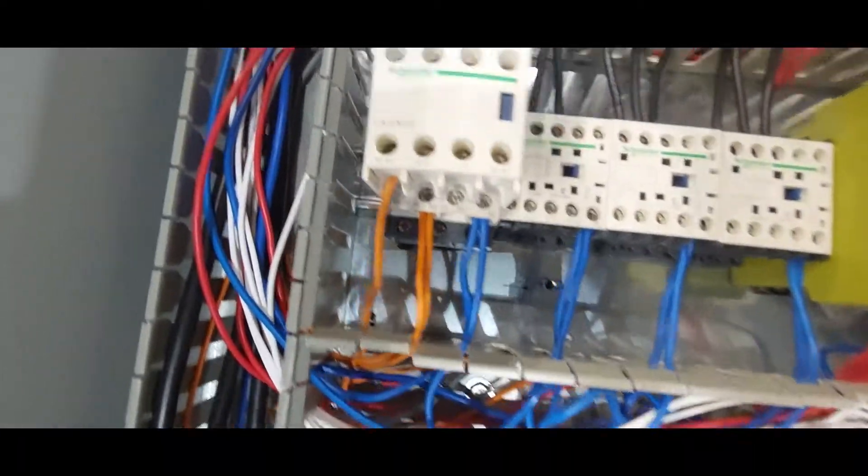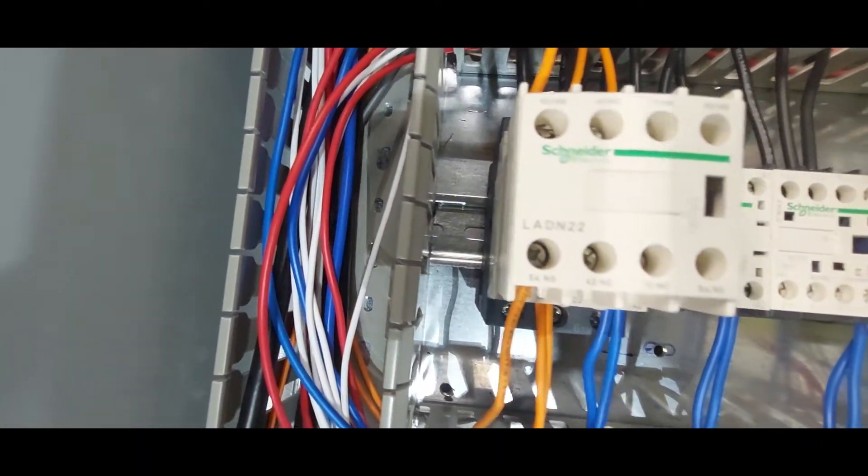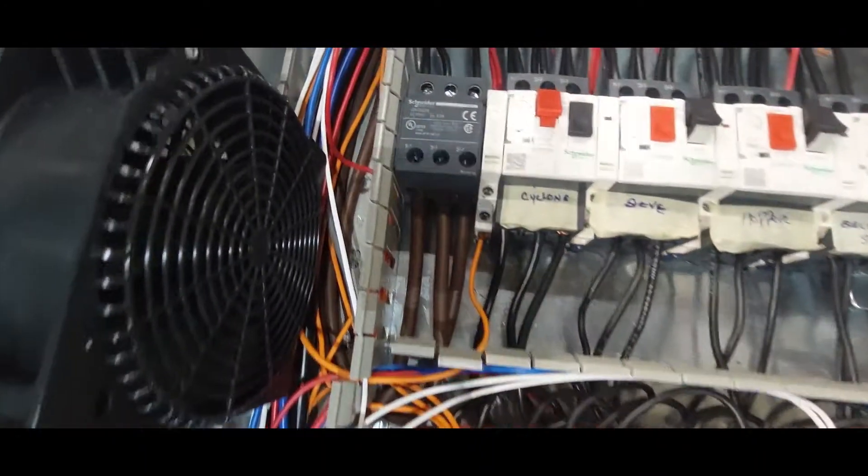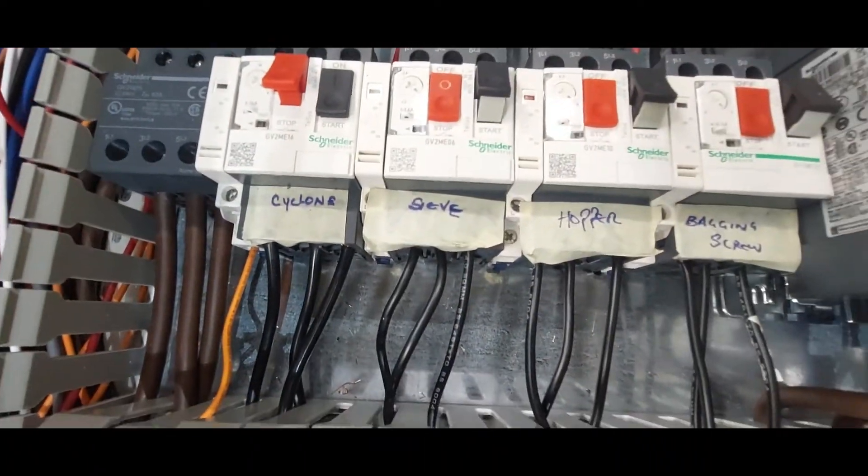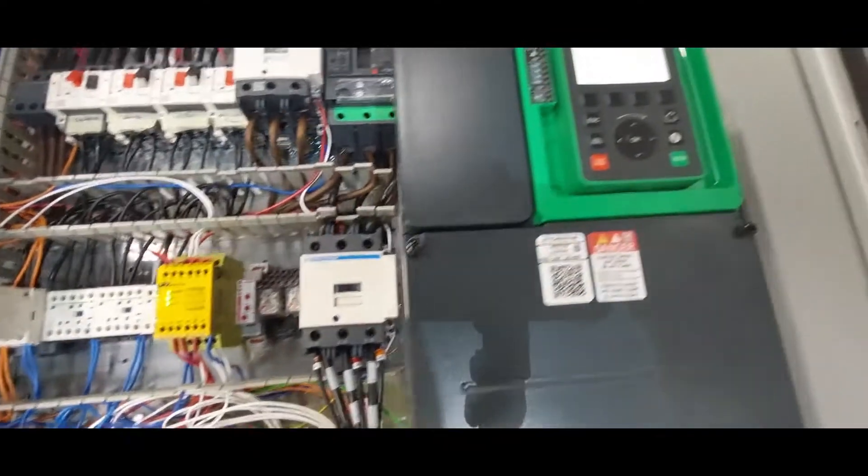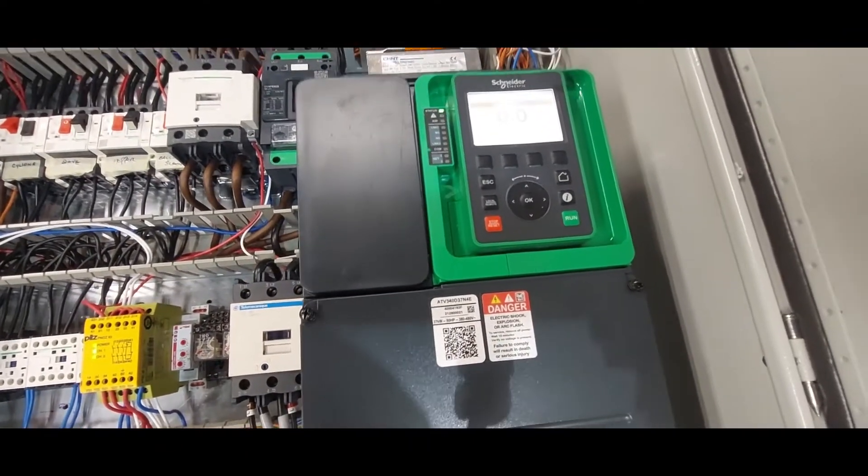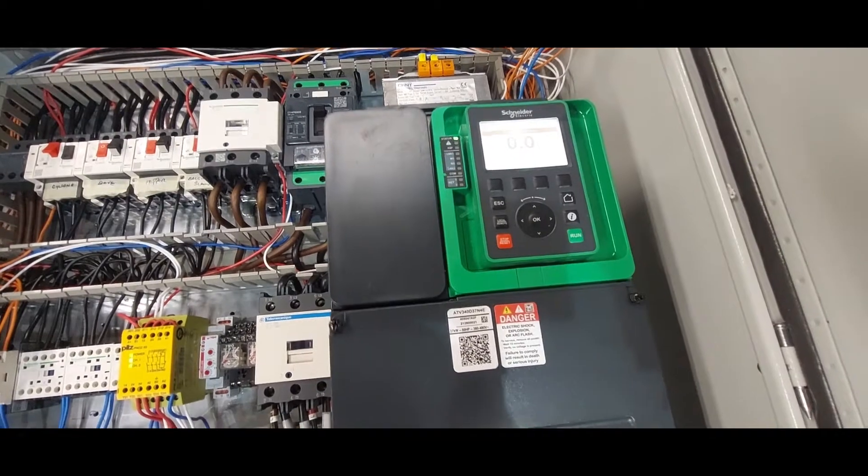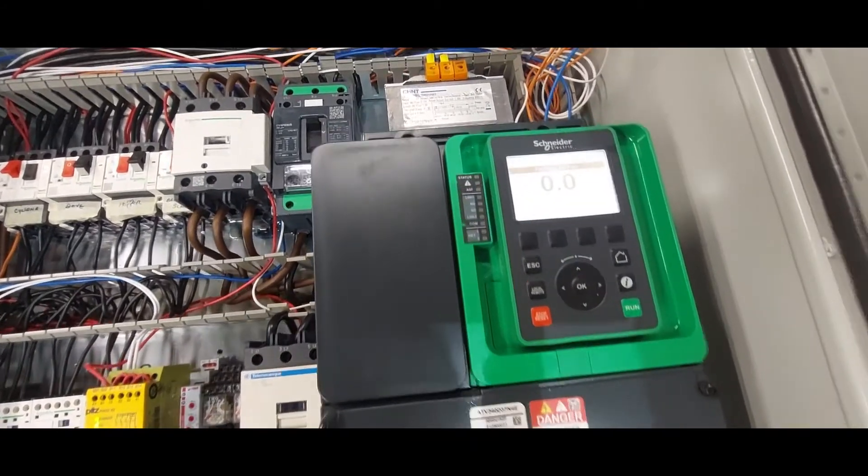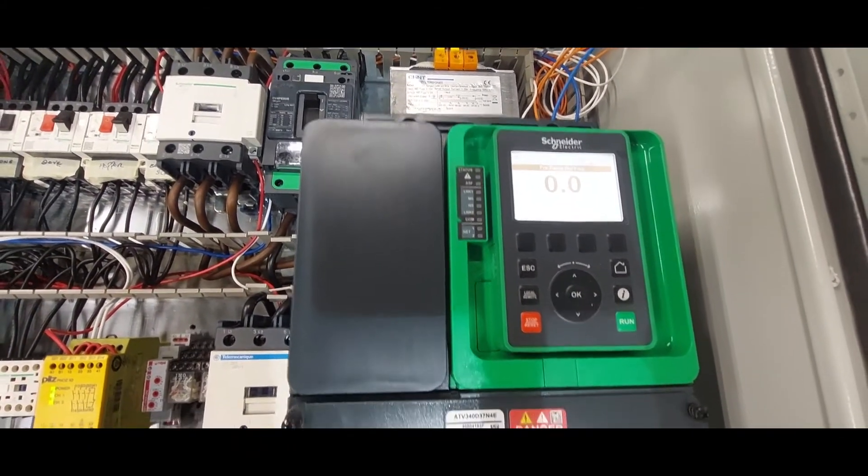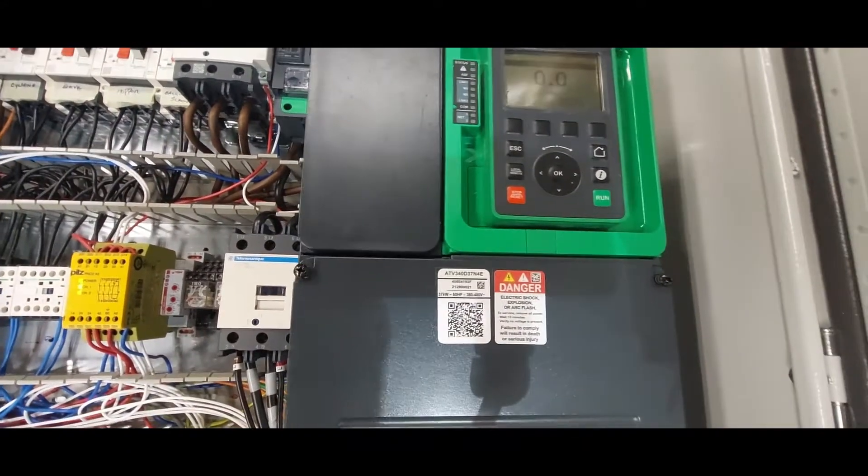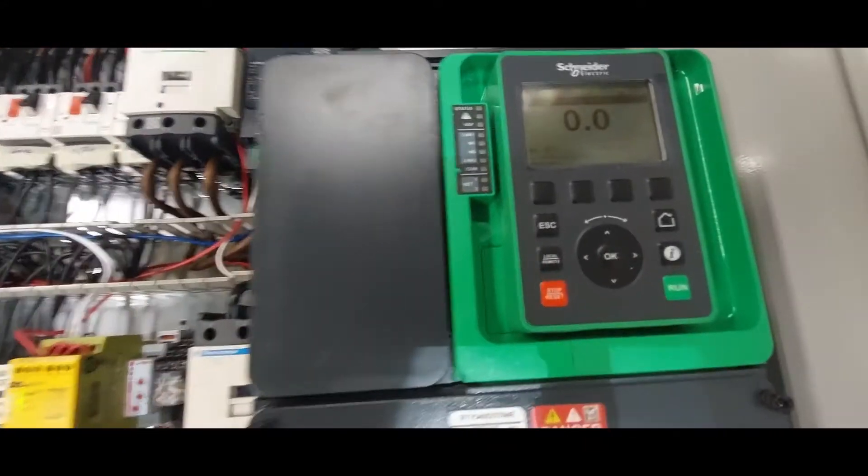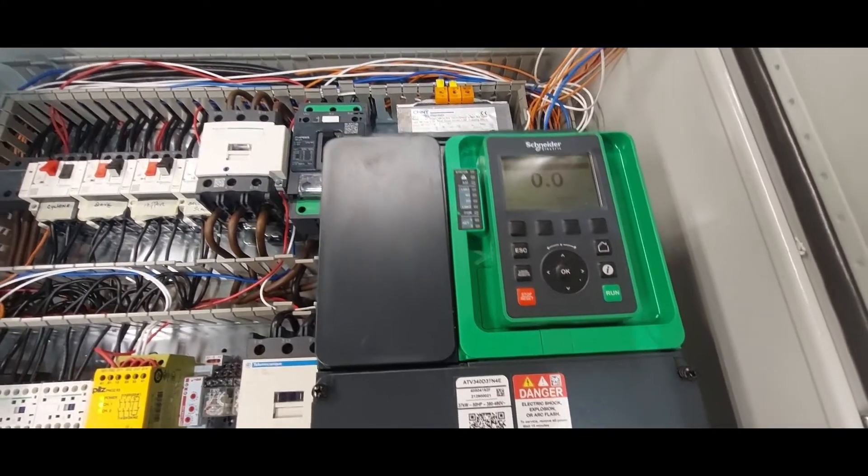So that's the cyclone. The cyclone is running. I still have to do all these machines: this one, two, three. But those three machines will now depend on this inverter because I want it to be started via RPM switch. So when this inverter reaches 50 hertz and the motor is running at full speed, then it will trigger these three motors.